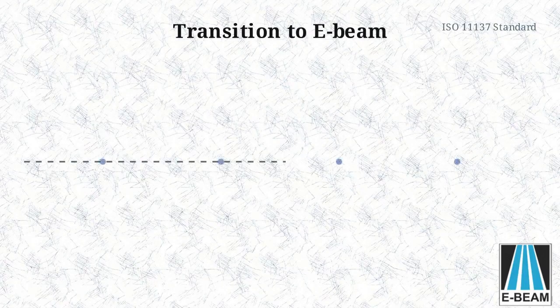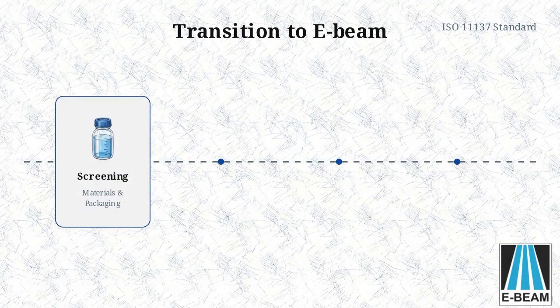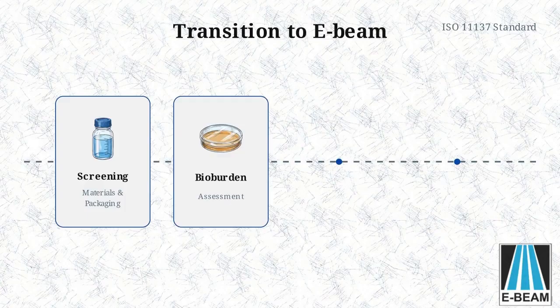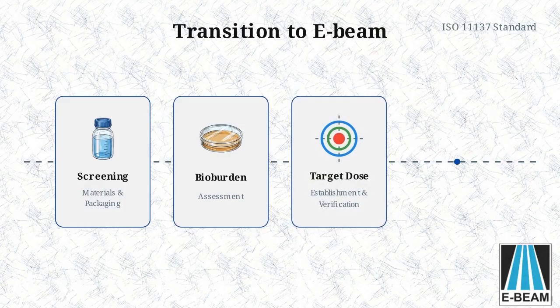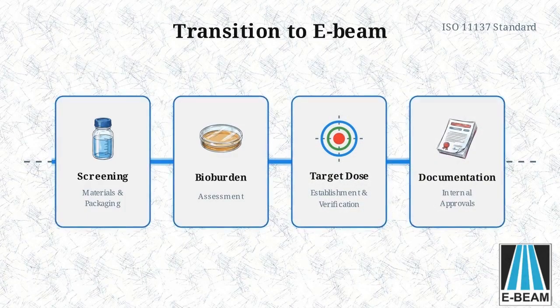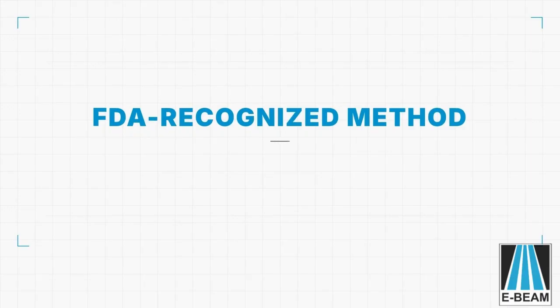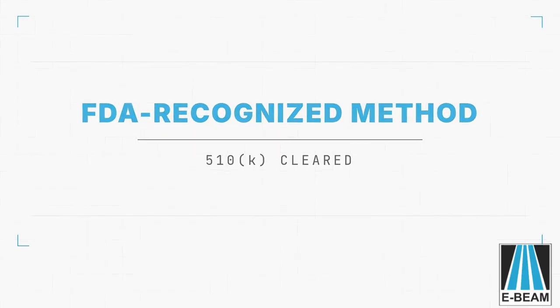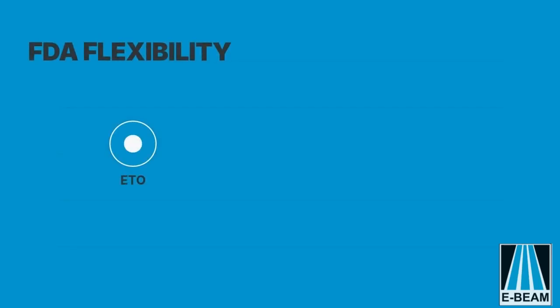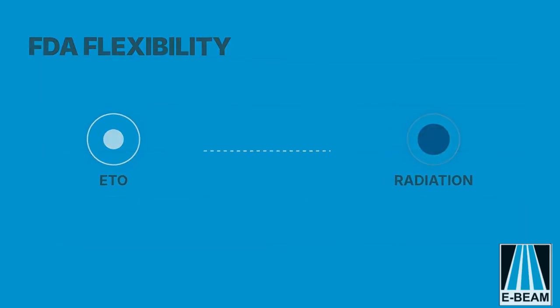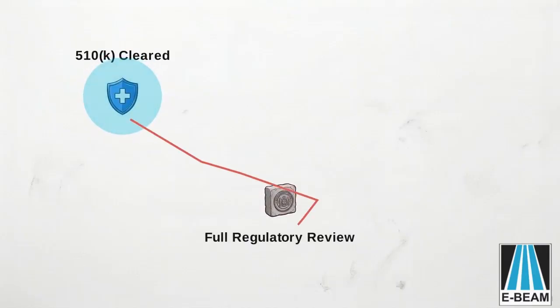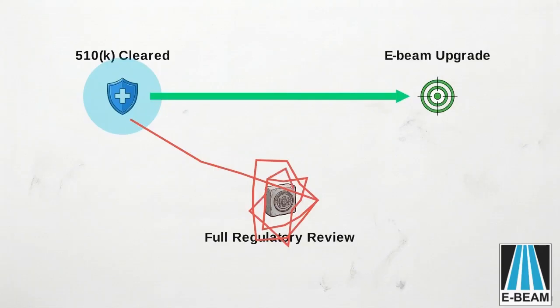The transition followed a straightforward sequence: material and packaging screening, bioburden assessment, dose establishment and verification, then documentation and internal approvals. On the regulatory side, electron beam is an established FDA-recognized sterilization method. For 510K cleared devices, FDA has signaled real flexibility when moving from EtO to radiation under controlled conditions. Some changes may not even require a new 510K.